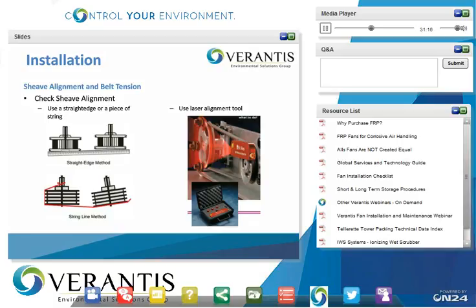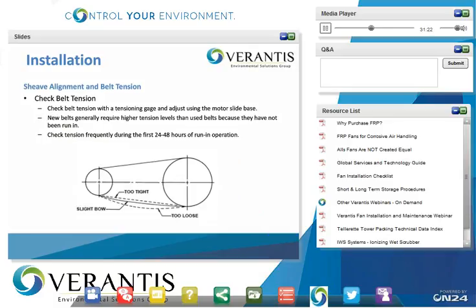Belt tension will be on the next page. You want to check your belt tension with a tensioning gauge and adjust using the motor slide base, whether it would be an arrangement 10 fan with the adjustable base mounted inside the base. There are still slots there that allow the motor to raise vertically or lower. And then the arrangement 9s have an actual adjustable motor base with jack bolts on it.